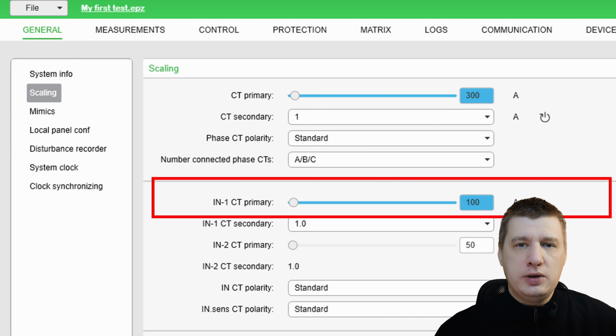Now, the In1 CT primary in the software, this is labeled In, which stands for residual or neutral current. This setting specifically is for earth-fault CTs. These CTs are usually connected to slot A, terminals A13 and A14. They are to detect leakage to the ground. Even if your main phase uses 300A CTs, your earth-fault CTs might be completely different, for example, 50 amps. Here are the main three things you should know.